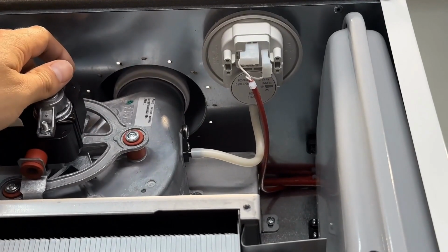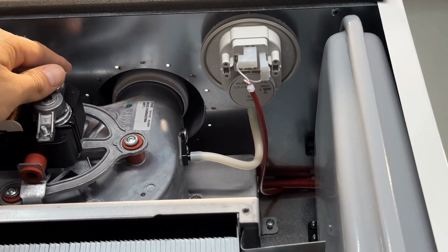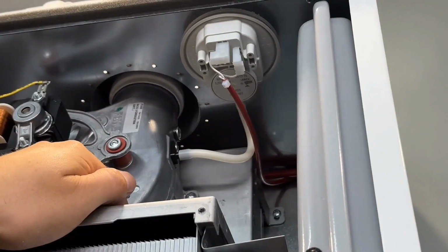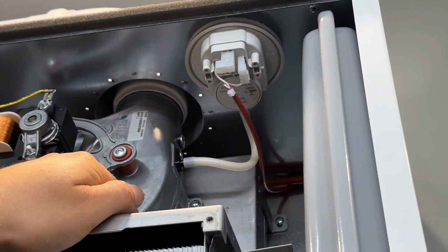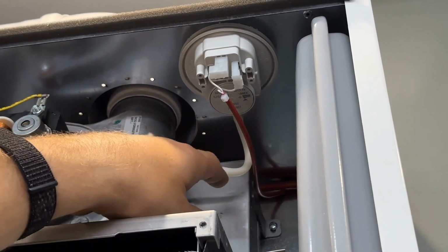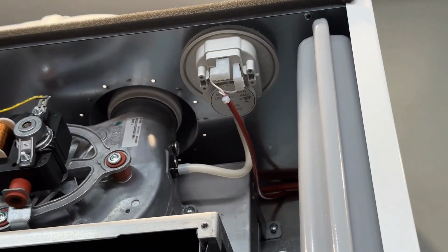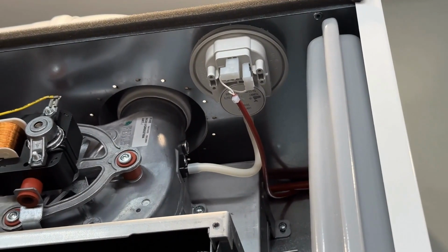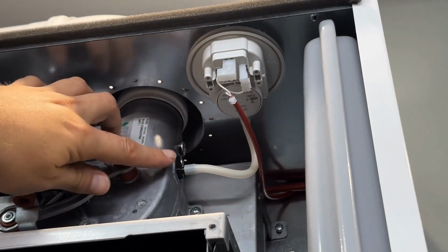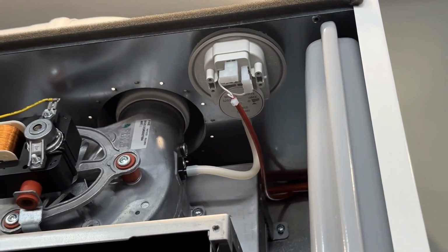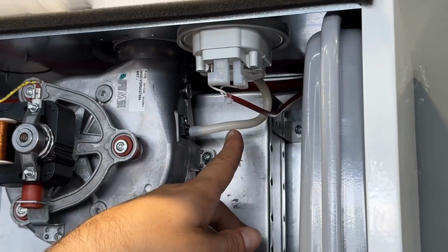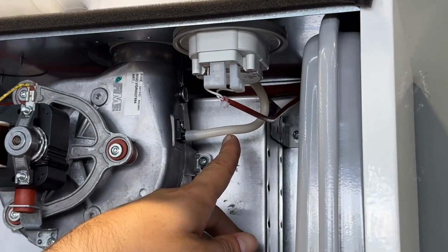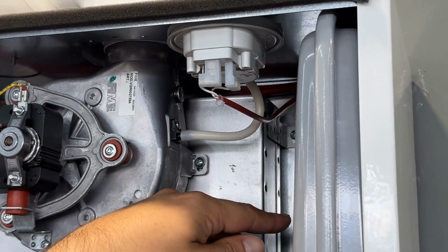But the most problems for people are caused by condensate that forms near the pressure switch. Despite the fact that pressure switches often operate under vacuum, due to diffusion, moist flue gases enter the impulse tube. At the same time, it is actively cooled by the incoming cold air from outside, which causes the formation of condensate droplets directly in the tube. And these droplets are often the cause of blockage and incorrect operation of the pressure switch.